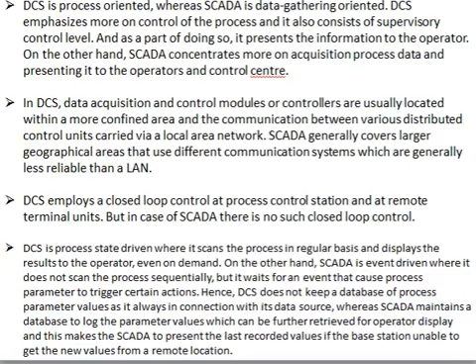In DCS, data acquisition and control modules or controllers are usually located within a more confined area, and the communication between various distributed control units is carried via a local area network. SCADA generally covers larger geographical areas that use different communication systems, which are generally less reliable than a LAN. DCS employs closed-loop control at process control stations and at remote terminal units. But in the case of SCADA, there is no such closed-loop control.